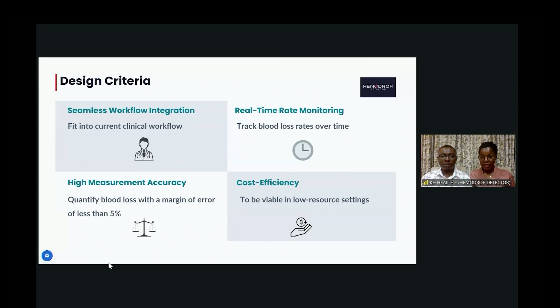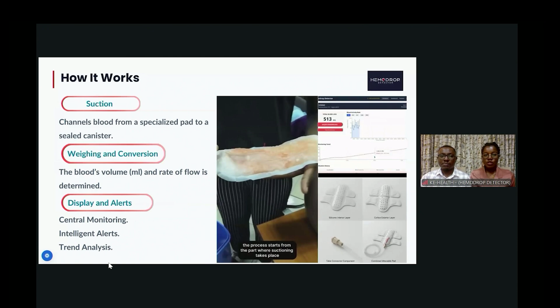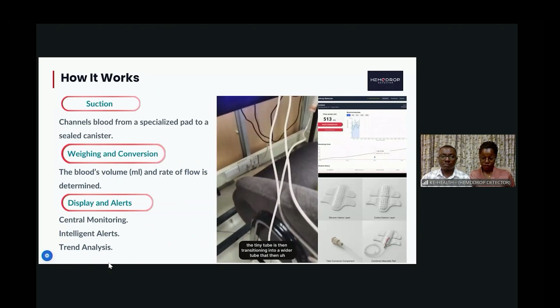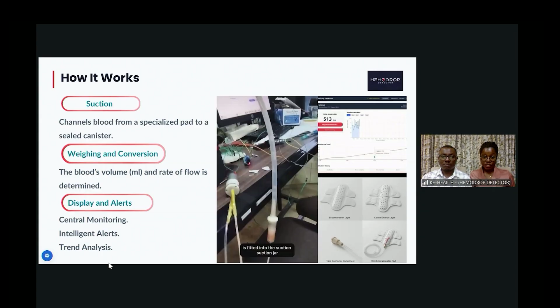Our design criteria: we designed this product to fit in the current clinical workflow, to quantify blood loss with a margin of error less than 5%, to have real-time rate monitoring, and to be cost efficient. How it works is blood is first suctioned from a specialized pad, and then it's channeled into a canister where it's weighed and converted to volume and also rate of flow. The data is then displayed at the bedside unit, which is hardware, and also at the central monitoring unit, which is preferably at the nursing station. Two things to note here are the intelligent alerts and also trend analysis for our device.